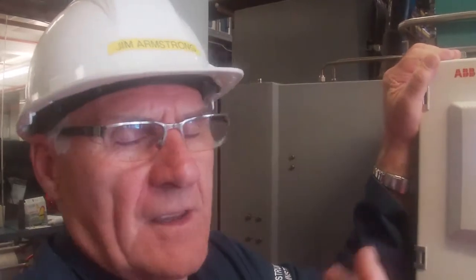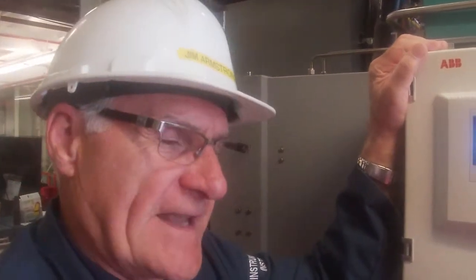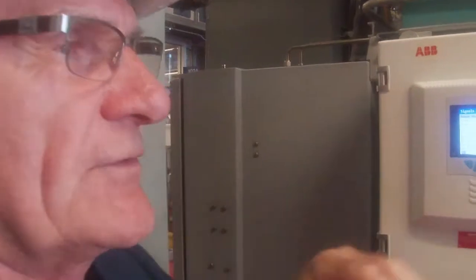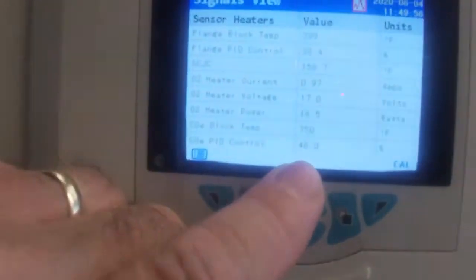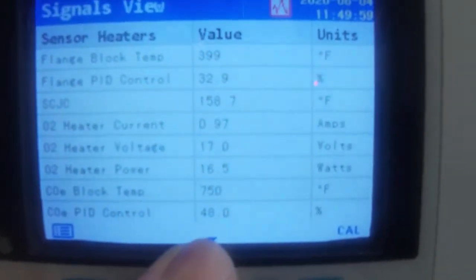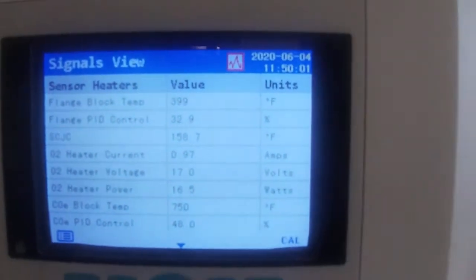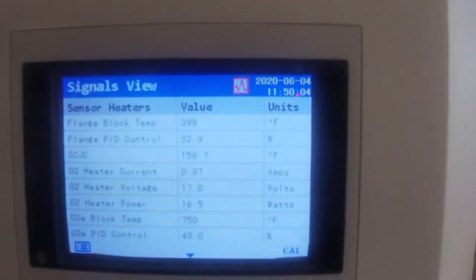measuring element is a catalytic type element where we're actually passing a current through it. And what it does is that it actually burns off carbon monoxide or hydrogen or whatever the combustible fuel might be, and it changes the temperature. There's a reference cell and a measurement cell. And for that to work properly, you need to be up at an elevated temperature. The temperature that ABB uses is 750 degrees. And it's again telling me the PID control for that block is sitting at 48% right now. So the block is up at the 750 degrees.